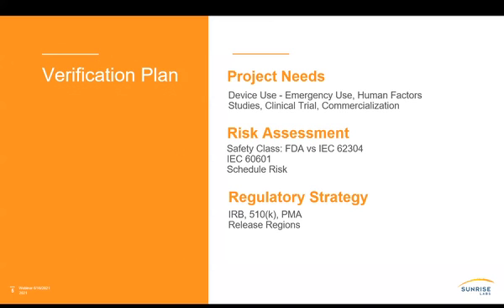But if you have some requirement in there that you've pointed to that says, you know, the device shall deliver fluid accurately, and your device shuts down, it's no longer delivering fluid. So now you have a real hard time getting through 60601 unless you make your device, in essence, fail safe. Like it has to keep performing even when failures occur. So it's definitely something to consider and put a lot of thought into as you're defining both essential performance and essential requirements. So that's kind of a wordy answer, but hopefully that was clarifying and not confusing.